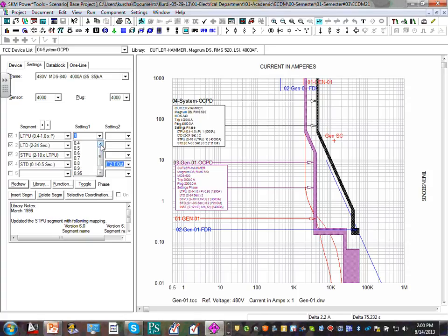So it depends upon the circuit breaker. 0.95 probably still doesn't get generated. So if I go there, what would that give me? 3,800. Isn't that 38? So you almost have to go to, you're absolutely right. You would have to, because your conductor is only 3,800 amps. You can't go to 4,000.